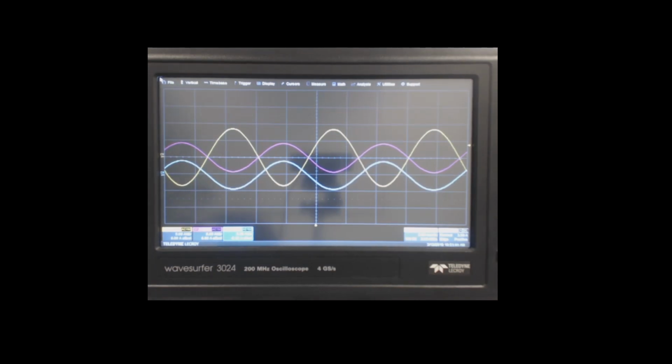In this example, we set 6 amps to each phase, but the waveforms of loads 2 and 3 are half the size of load 1. Since the loads are running independently, we can change the load level and even the crest factor of the second phase without affecting the first.